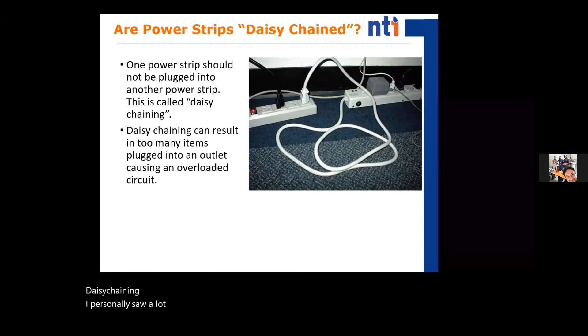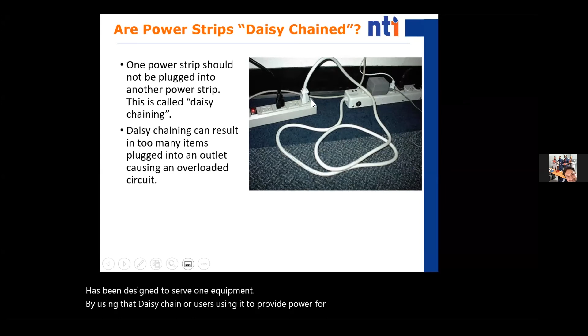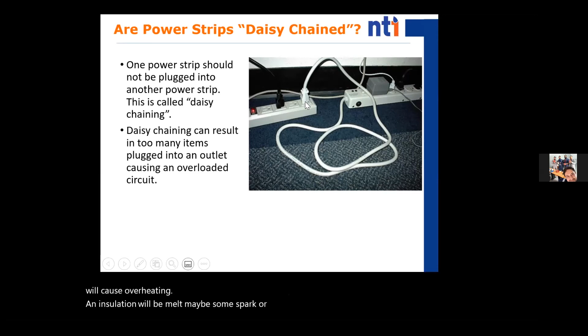Daisy chaining - I personally saw a lot of such cases. We have an extension, and from that extension we start another extension. This is totally wrong and unsafe, because this block has been designed to serve one piece of equipment. By daisy chaining or using it to power another extension, you are overloading this point with multiple devices - 1, 2, 3, 4 - while it was designed only for one. That will cause overheating, and the insulation will melt, and possibly some spark or heat source will come, which is a potential risk.